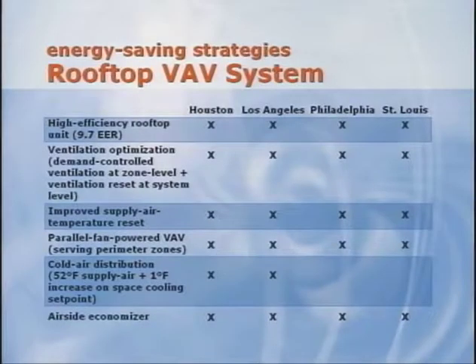For Philadelphia, the same set of strategies was used to achieve 24% energy cost savings. For both Houston and Los Angeles, the system was designed for cold air distribution, 52 degrees supply air compared to the conventional 55 degrees. In Houston, this was needed in order to get beyond the minimum threshold of 14% with a rooftop VAV system. But you probably noticed on the chart that even with cold air distribution, the proposed building in Los Angeles did not reach that minimum threshold.